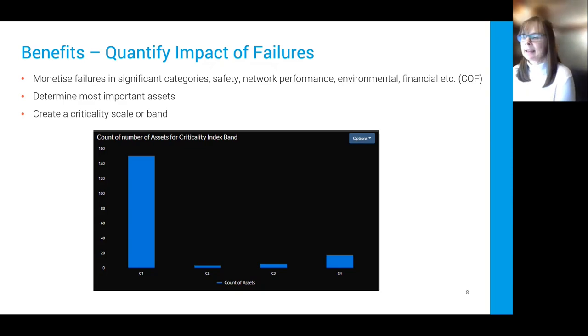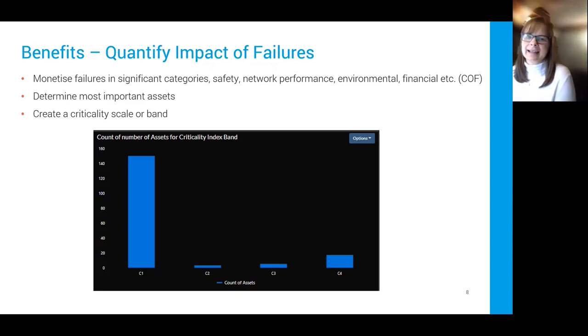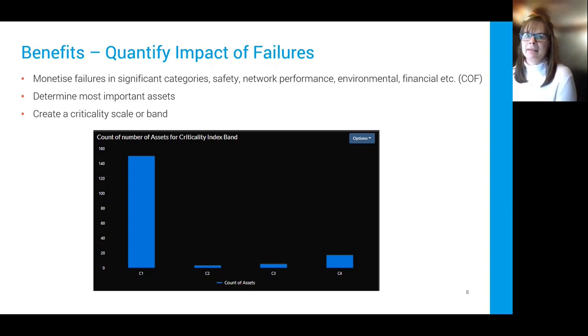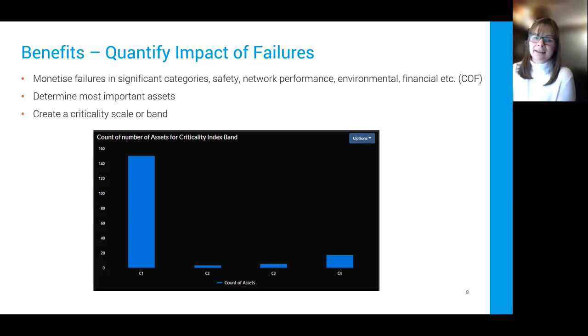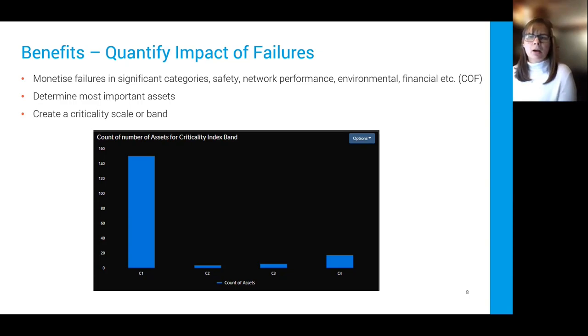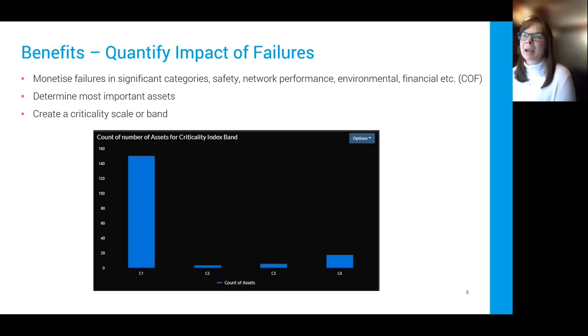The next benefit is to quantify the impact of failures. The common methodology uses a criticality index: a value of one represents an average asset, and higher values indicate increasing criticality — meaning the importance of the asset. Some assets feed more customers; some have greater environmental consideration. For example, oil-filled cables in severely degraded condition often have higher risk due to higher environmental consequences. It's quite useful to create a band or scale to represent health and criticality.